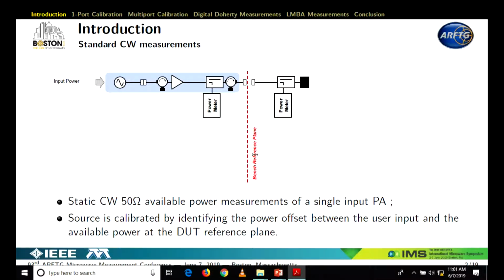First of all, I would like to talk about very basic measurement with a power sensor in CW mode. Basically, we define a reference plane, here displayed in red, and we have two power sensors, one for the input and one for the output. We just have to identify an offset between our power sensor and that reference plane. This is for basic CW measurement.